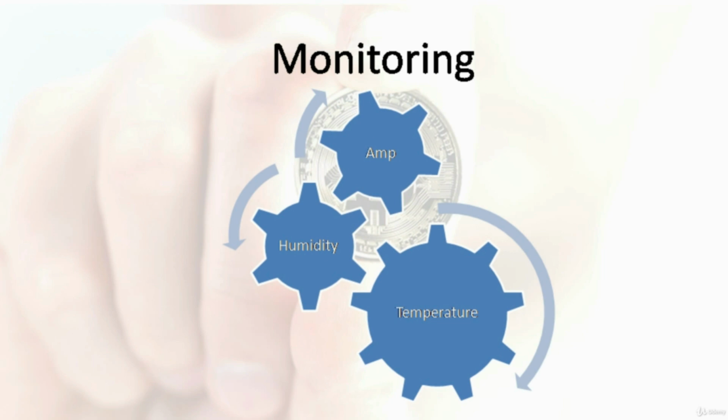Too much moisture in the air will cause accelerated corrosion to your equipment, and too dry may cause static electricity problems. However, don't worry too much about this, as we only need to monitor extreme conditions in the case of humidity. The third type of sensor that I would recommend is the amp meter that can be installed in the power strips of your racks or cabinets. These meters display the electric load that is put on them.